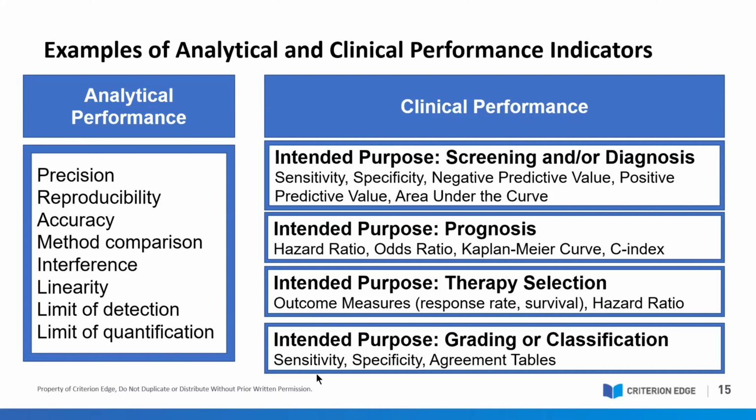Specifically, the term clinical study by itself, if they have not clearly specified whether it's an analytical or a clinical performance study, can be confusing. It's sometimes applied to any study that uses a patient sample or a clinical sample, independent of the performance indicators that have actually been presented. So just remember that an analytical performance study that uses patient samples is not a source of clinical performance data. The recommendation, therefore, is to make sure that you are properly using and distinguishing between the types of data so that they can be presented separately within the different reports, the APR and the CPR.